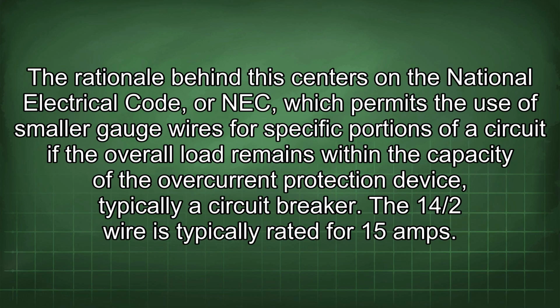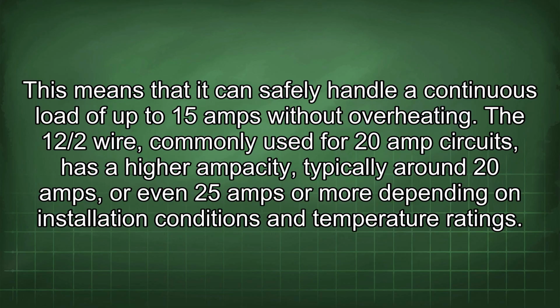The rationale behind this centers on the National Electrical Code, or NEC, which permits the use of smaller gauge wires for specific portions of a circuit if the overall load remains within the capacity of the overcurrent protection device, typically a circuit breaker. The 14/2 wire is typically rated for 15 amps. This means that it can safely handle a continuous load of up to 15 amps without overheating. The 12/2 wire, commonly used for 20 amp circuits, has a higher ampacity, typically around 20 amps, or even 25 amps or more depending on installation conditions and temperature ratings.